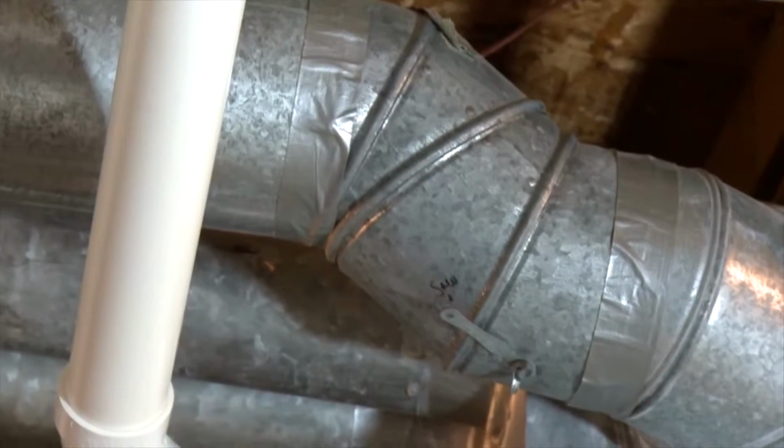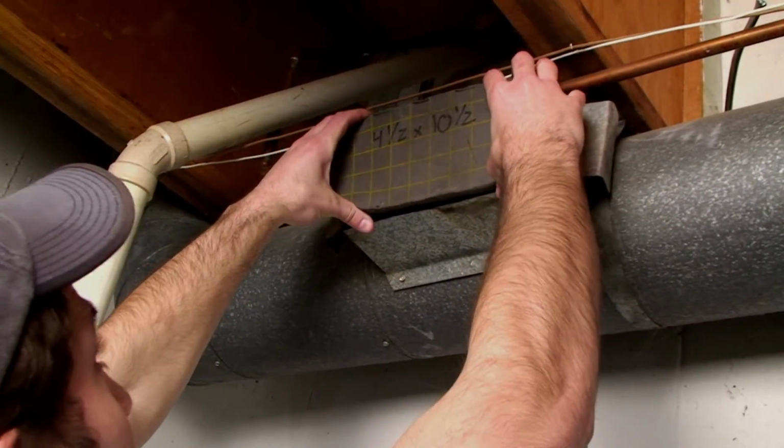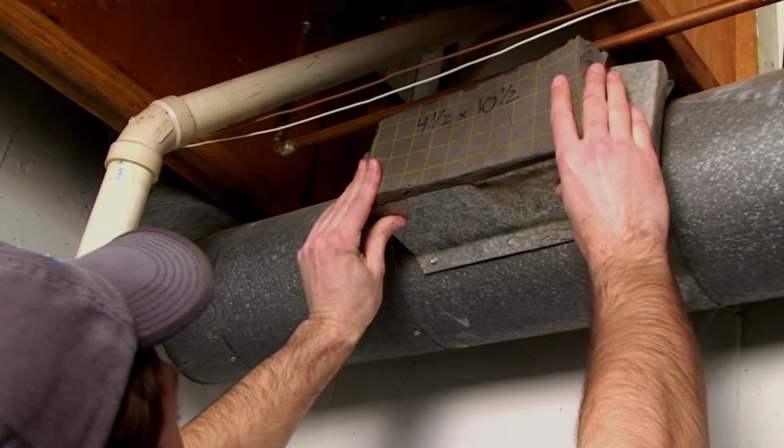I tried using all the conventional methods to correct the problem. I tried to use duct tape, caulking, especially on all the ductwork that I could see in the basement. But all of this was ineffective because the air leak itself was actually coming through the walls and not the ductwork.